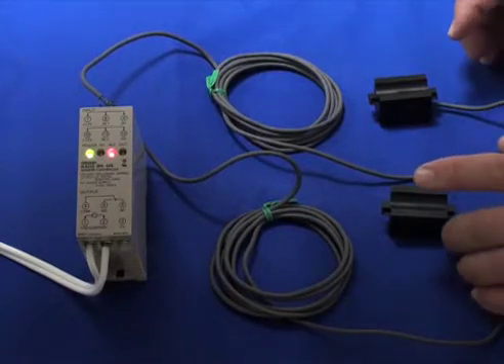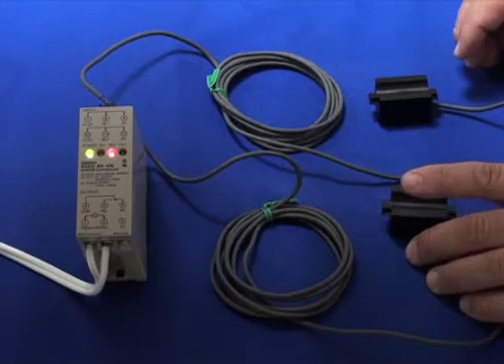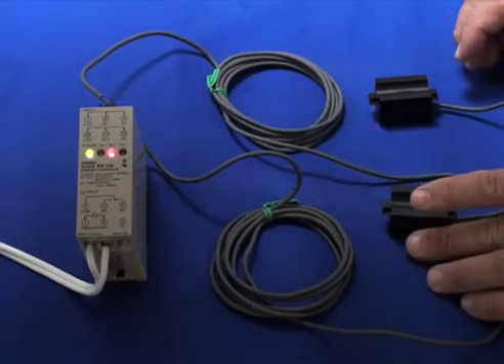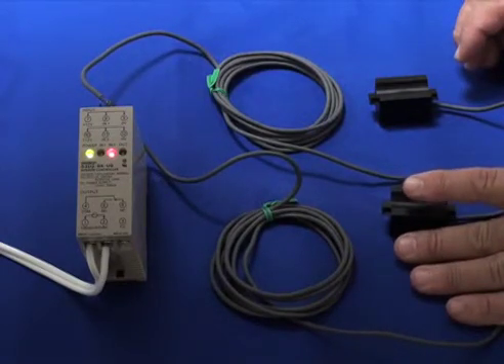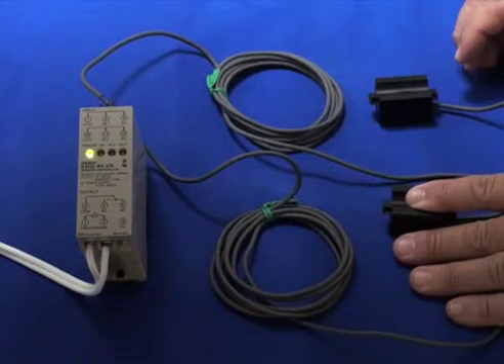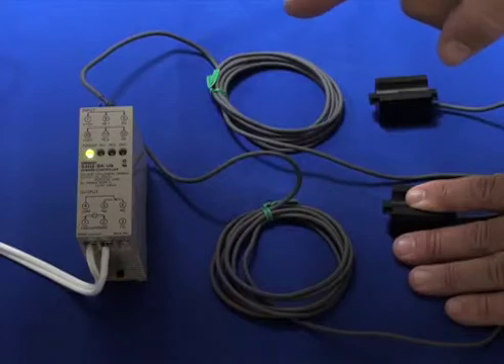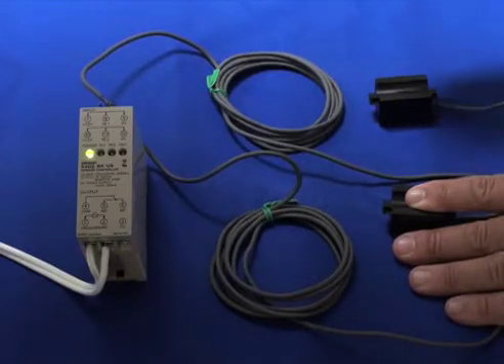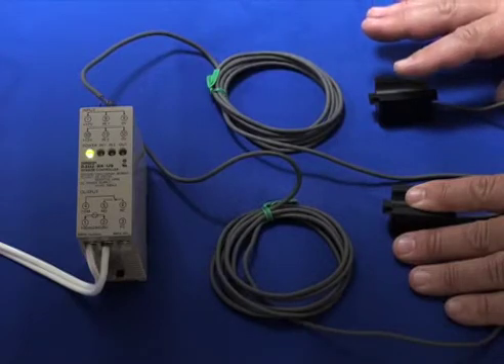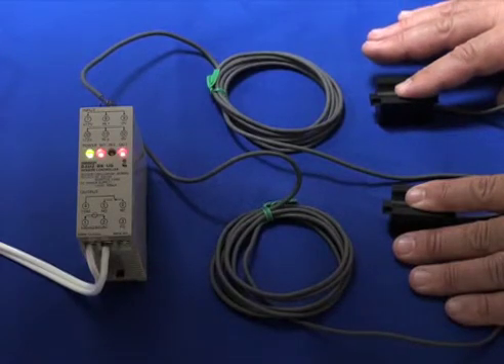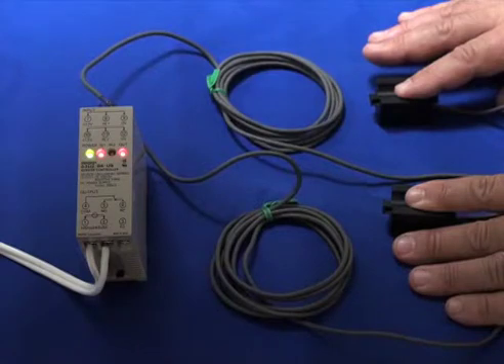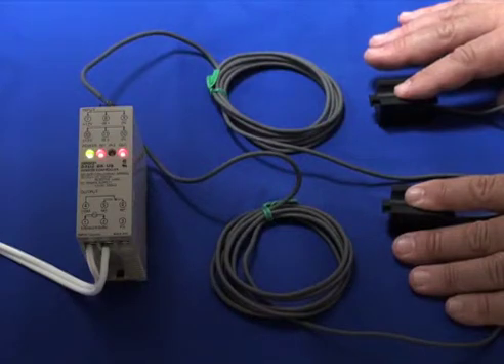In this case, the bottom sensor is the low level sensor. As the wastewater starts to enter into the vessel, my low level sensor turns on and the inverted logic makes the light turn off on the sensor controller. The water is filling until I reach the high level sensor, and I have an input indication on input one and I also have an output. You heard the relay click, which is your signal to turn on a pump and start pumping out water.